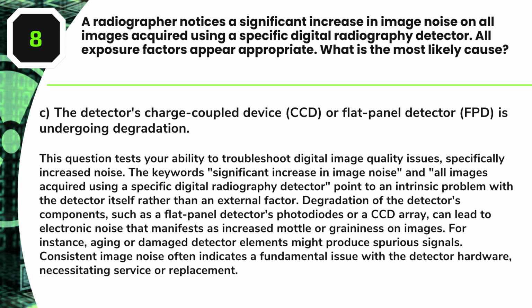Answer: C. The detector's charge-coupled device, CCD, or flat panel detector, FPD, is undergoing degradation. This question tests your ability to troubleshoot digital image quality issues, specifically increased noise. The keywords significant increase in image noise and all images acquired using a specific digital radiography detector point to an intrinsic problem with the detector itself rather than an external factor.